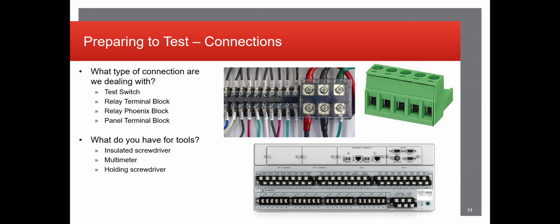It's pretty simple. If the test switches aren't available, or they're an older model that doesn't allow you to jack in with your plug, sometimes you have to go straight to the back of the relay. Or if you're doing a bench test and the relay is not even installed yet, you'll have to connect directly to the back of the relay terminal blocks. This isn't terrible, but it can be time consuming and a little tedious to put your cables into every single output, input, voltage, and current terminal. It also gets frustrating to have to change the outputs depending on what test you're running, so it ends up being pretty time consuming.